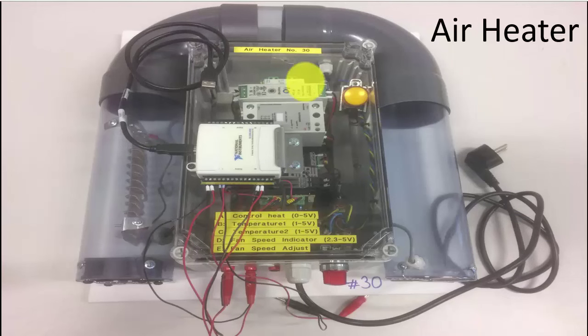And if the mathematical model used in the simulator is an accurate representation of the real process, you may use it to tune the controller and find the PID parameters using the simulator. So here is our setup. We have the mathematical model in our PC using LabVIEW to implement the model. And then we use a DAQ device to send the output of the mathematical model to the real PID controller, and then the control signal from the PID controller is sent back to the mathematical model, which is in our PC.